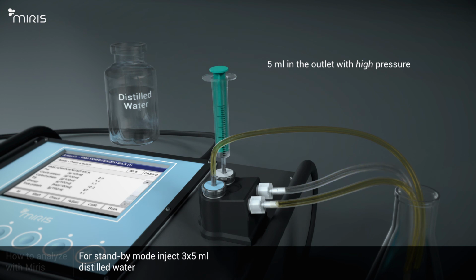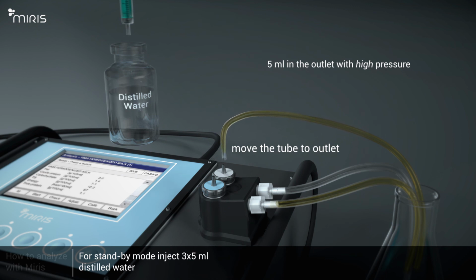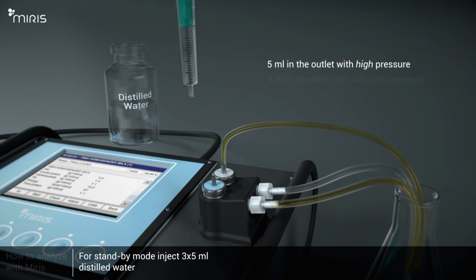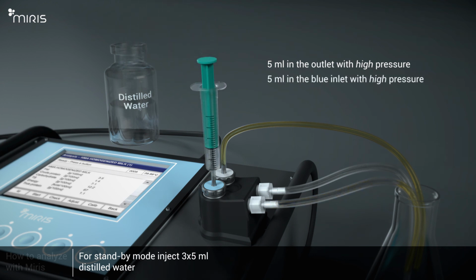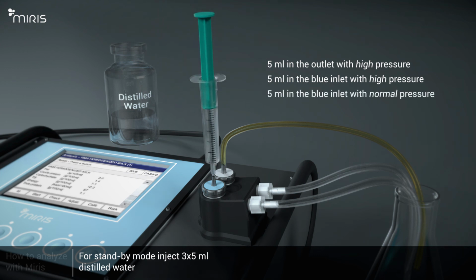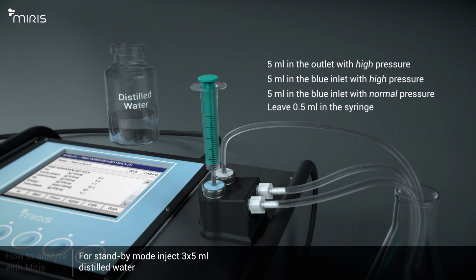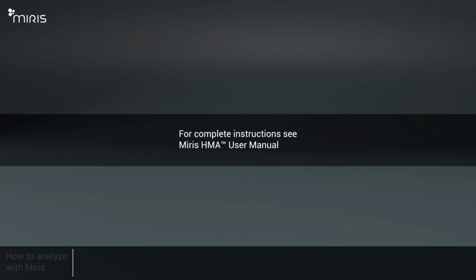Inject 5 milliliters into the outlet with high pressure. Inject 5 milliliters into the blue inlet with high pressure. Inject 5 milliliters into the blue inlet with normal pressure. To store the instrument, leave the syringe filled with 0.5 milliliters attached to the inlet. For complete instructions, see Miris HMA User Manual.